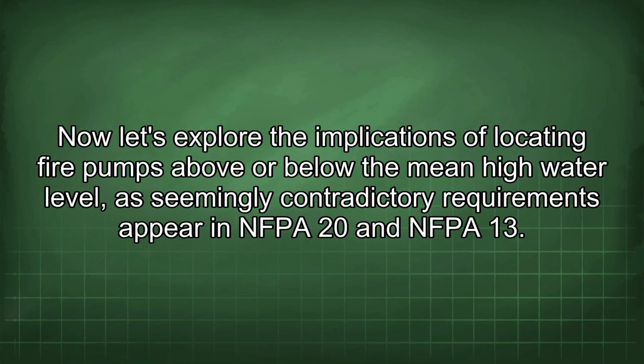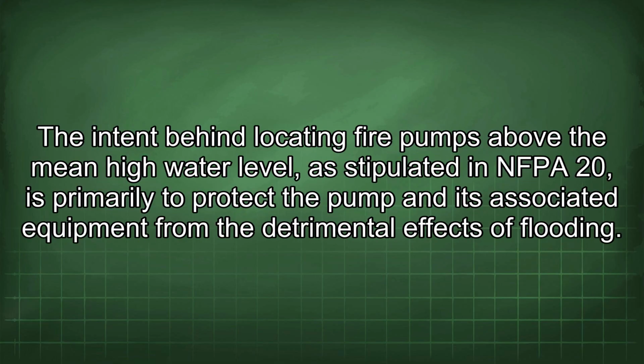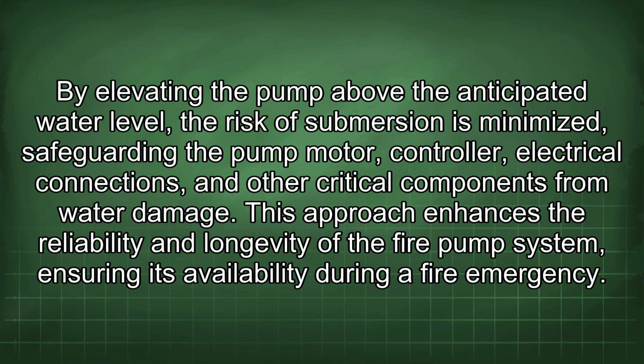Now let's explore the implications of locating fire pumps above or below the mean high water level, as seemingly contradictory requirements appear in NFPA 20 and NFPA 13. The intent behind locating fire pumps above the mean high water level, as stipulated in NFPA 20, is primarily to protect the pump and its associated equipment from the detrimental effects of flooding. By elevating the pump above the anticipated water level, the risk of submersion is minimized, safeguarding the pump motor, controller, electrical connections, and other critical components from water damage. This approach enhances the reliability and longevity of the fire pump system, ensuring its availability during a fire emergency.